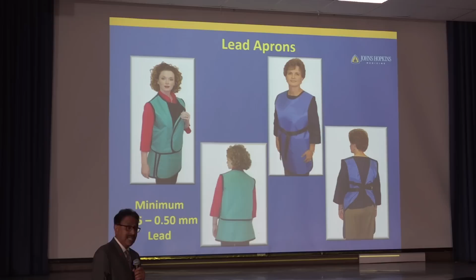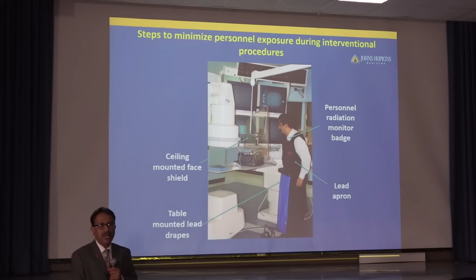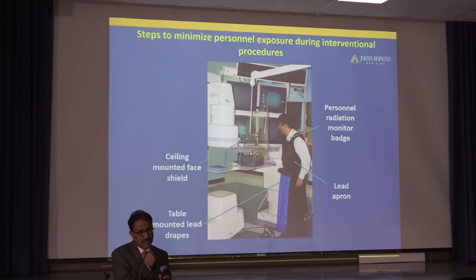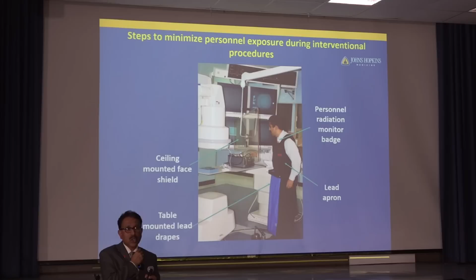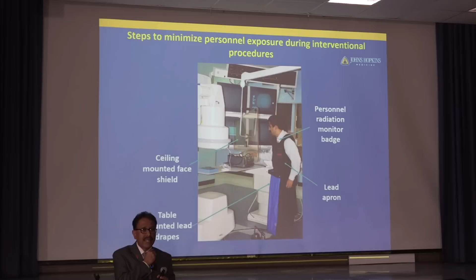With the aprons that wrap around, 0.25 to 0.5 millimeter of lead is quite sufficient, and most rooms should have these ceiling mounted shields. Positioning the ceiling mounted shields will protect the uncovered portion of the body pretty much. In the US, you are required to wear the badges outside the apron, so the idea is to monitor what the uncovered portion of the body is getting, and that's routinely monitored by regulation so that it does not exceed the limitation. And even then the limitations are set at a very conservative level, so one should not be totally worried if they get any radiation.